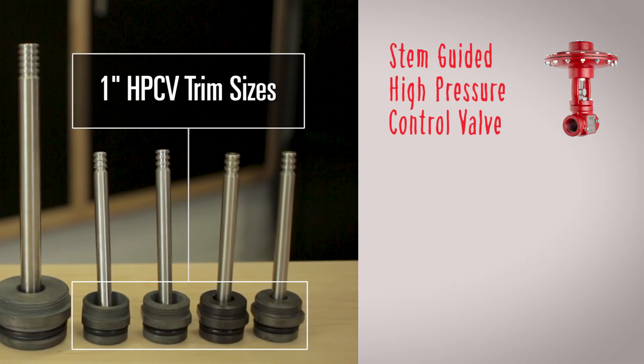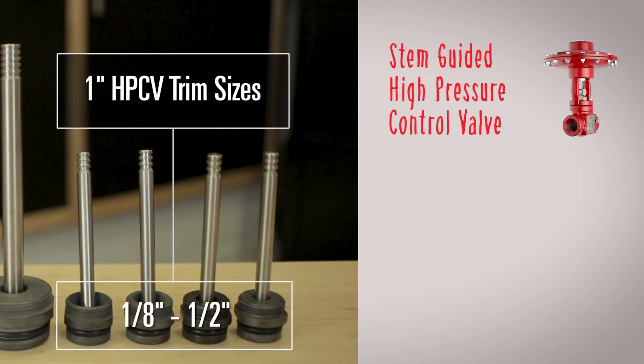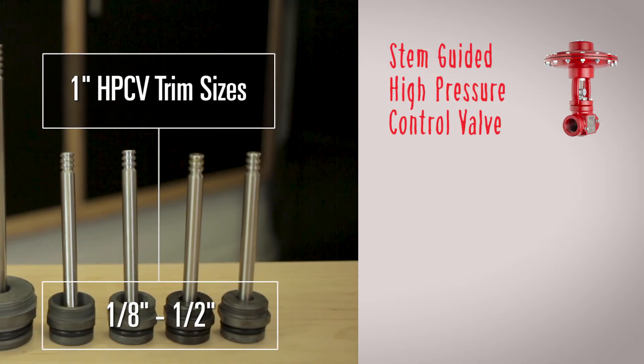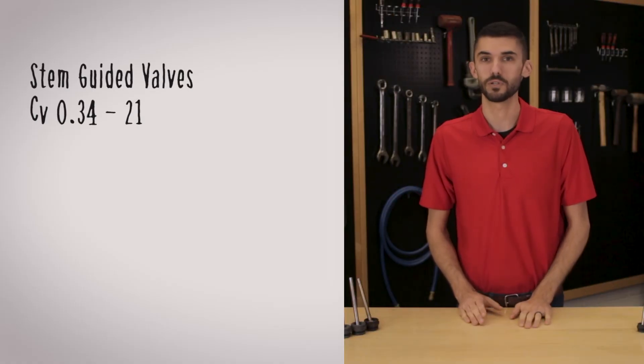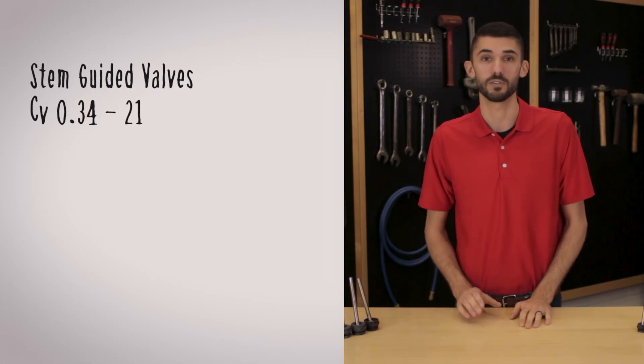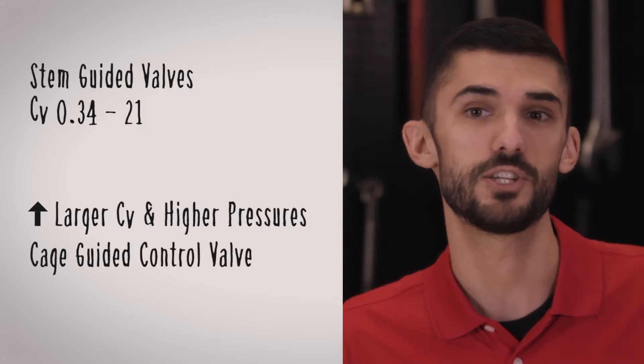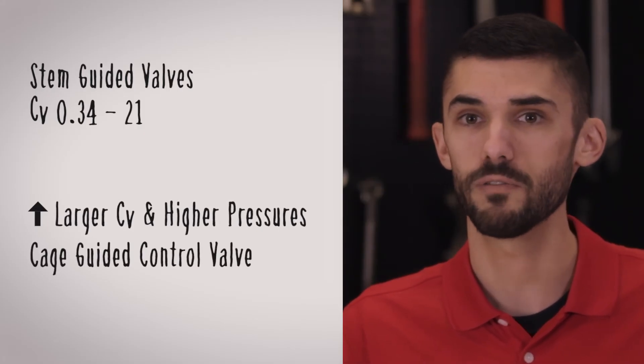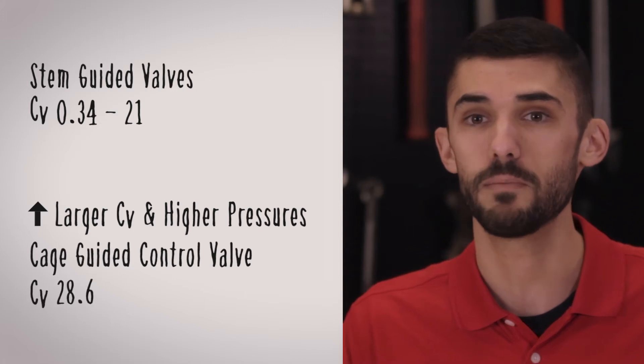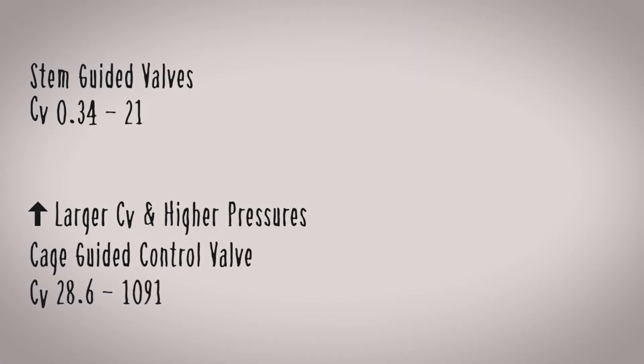Our 1-inch stem-guided valves come with trim options ranging from one-eighth inch to half inch. Stem-guided valves have small CVs from 0.34 to 21, and they can handle low flow as well as high pressure drop applications where you have a small CV requirement. For larger CVs and higher pressures, use Kimray's cage-guided control valves — they're a full port valve with CV ranges from 28.6 to 1,091, available in 2-inch through 10-inch sizes.